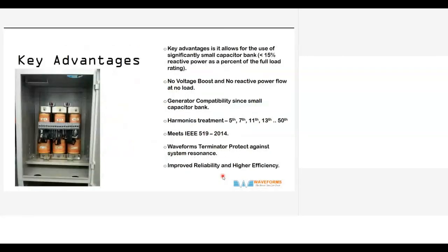So the key advantage is it allows the use of a significantly small capacitor bank. As I told you, in other tuned filters, the capacitor rating will be very high. So if the load is constant, there's no issue. But if the load falls down, there can be overcapacity. And when you have overcapacitance, then you can have resonance and then ringing and all that. So it can complicate the entire thing. So that disadvantage is removed with this type of universal filter because it is 15% only.